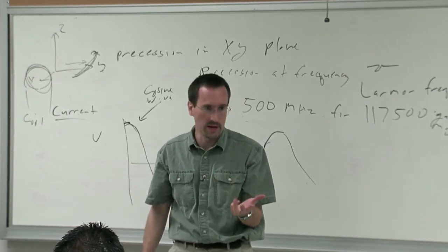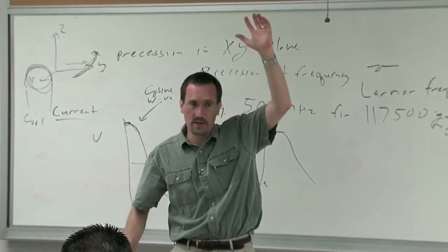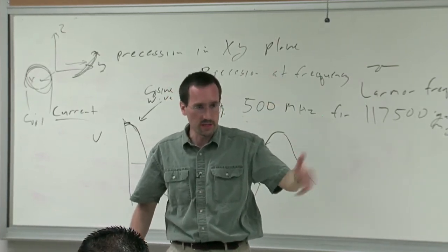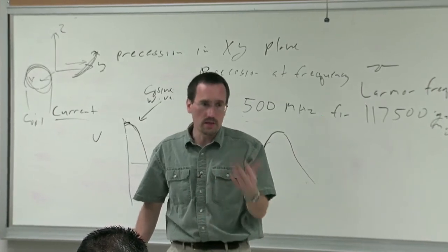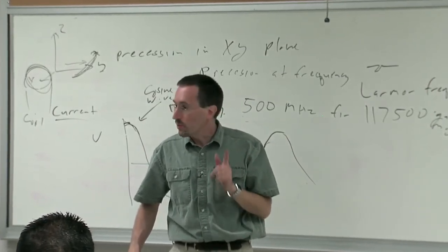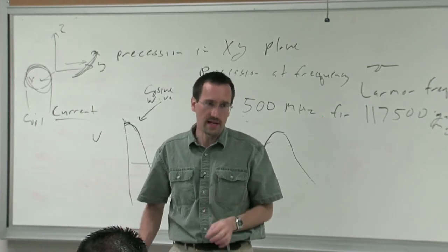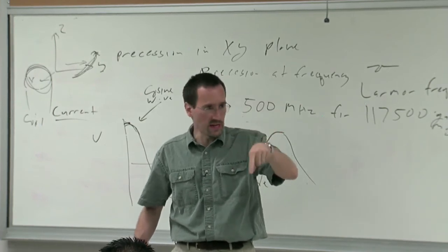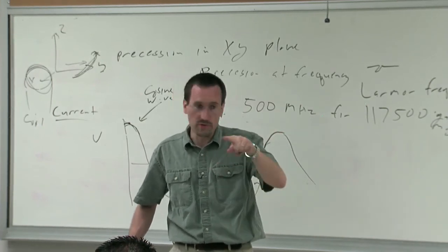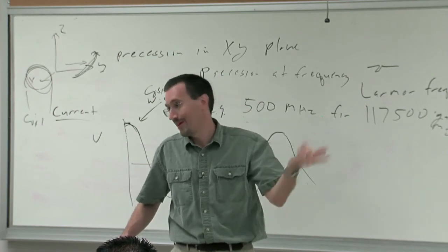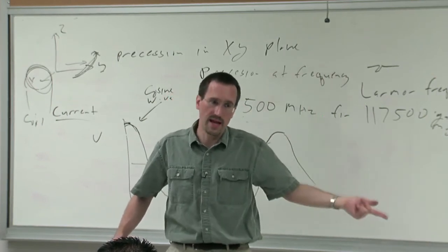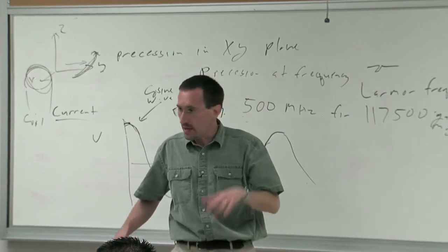So for those of you who've run a spectrometer, how many of you have run an NMR spectrometer? And you do number of scans is equal to 4 or 8 or 16, that's no accident, because we are actually doing what's called phase cycling, which means in order to cancel out artifacts, we do a set of 4 experiments or 8 experiments. So you first do a positive X pulse, for example, then you do a negative X pulse, then a positive Y pulse, then a negative Y pulse. And then we average them all together, and that reduces artifacts.